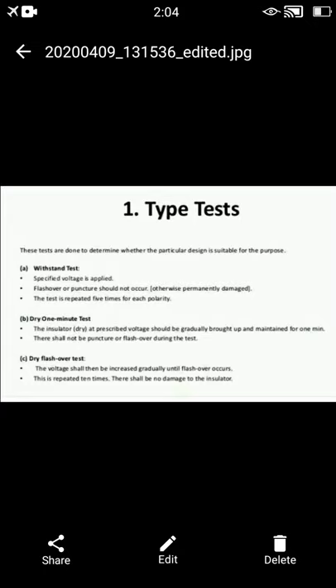Let's discuss the first type of test, called the type test. In this test, there are five different sub-tests. The first is the withstand test, the second is the dry one minute test, the third is the dry flashover test, the fourth is the one minute rain test, and the fifth is the wet flashover test. In the withstand test, a specified voltage is applied to the insulator, from which flashover or puncture should not occur, otherwise the insulator is permanently damaged. This test is repeated five times for each polarity of the device.